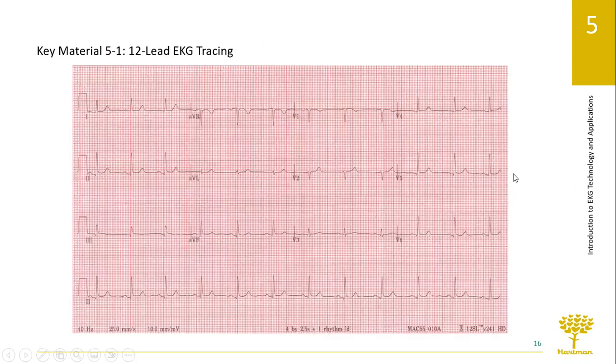So here on our 12 lead, on the very left of it, there's a 10 millimeter deflection, and that's it right there. So anytime you see that, that tells you that the cardiac monitor is calibrated correctly. So that's a little 10 millimeter deflection that means that we're calibrated and we're in ×1. And that means it's not been zoomed in or zoomed out. So what you see is the actual size of the impulses.